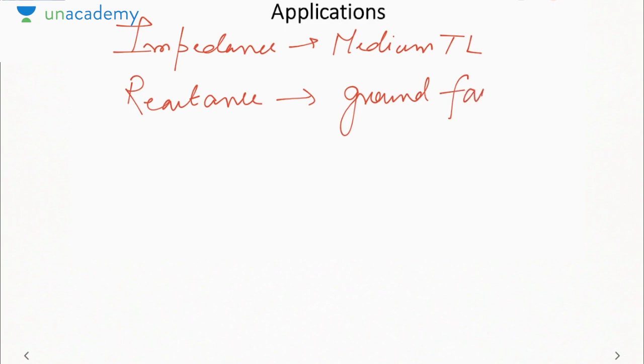Why against ground faults? Whenever a ground fault occurs on a transmission line, the resistance from the line or from the apparatus to the ground can be variable. Suppose a tree branch falls on the transmission line, due to which it gets connected to the tower. Then the resistance of that tree branch is unknown and variable. That is why, whenever we have variable resistance, it is better that relay operation does not depend on resistance. In that case, we can use a reactance relay.